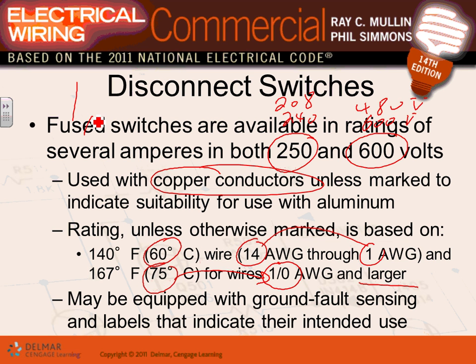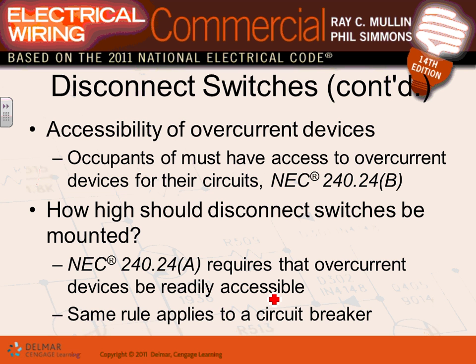They also have switches that go with the circuit breakers. These are basically the switches right here that go with the fuses, that combo. These also, guys, can have ground fault protection, where you sense a ground fault and trip the circuit breaker based on it. Ground fault protection, all it does is look at the ground fault. It doesn't care about phase-to-phase or 3-phase. If you have a ground fault condition, it trips. If you don't have a ground fault condition, it doesn't care. Not this project. Next project, guys, you will be installing ground fault protection with Visual. Hopefully, you guys will come when we start using Visual.